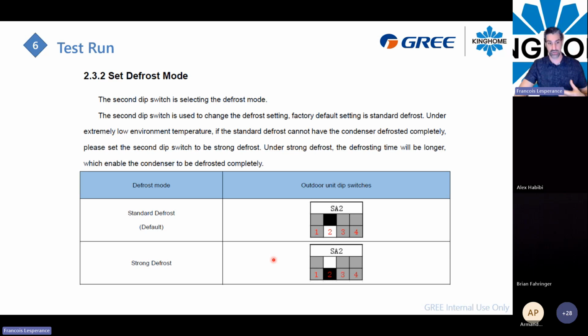If in your region or kind of installation you have some difficulty with the defrost, that's the thing to do. At first, put the power off, flip dip switch number 2 off, then bring the power back on and test your defrost.